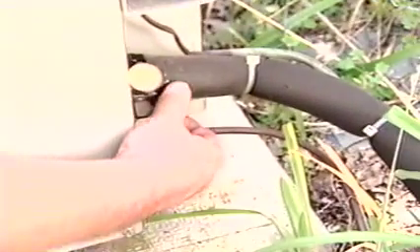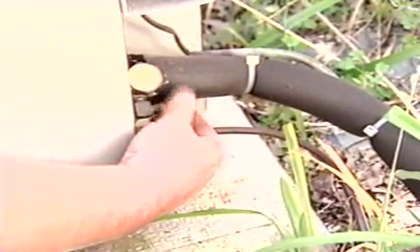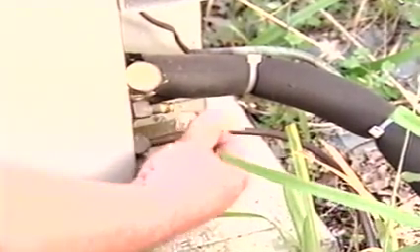Okay, you've now found the root cause of the problem, but there could be another problem. Shorted motor windings produce heat, and if there's enough heat, it could burn the refrigerant, and that can form hydrochloric and hydrofluoric acids. So when you find that a compressor has a shorted or open winding, always use an acid test. In this case, the acid test confirms that the system is not contaminated with acid, so you can go ahead with replacing the compressor. But first, explain the problem, estimate what a new compressor installation will cost, and get the customer's approval.